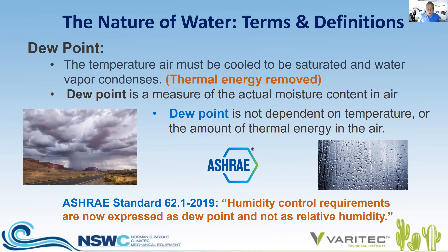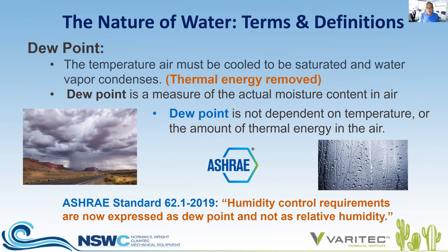ASHRAE 62.1 2019 states humidity control requirements are now expressed as dew point and not as relative humidity. I was always raised with relative humidity as a measure of the amount of moisture in the air — so why has ASHRAE moved away from it? Relative humidity is defined as a measure of water in the air in respect to the amount of water air can hold — 100% RH — at a given temperature.